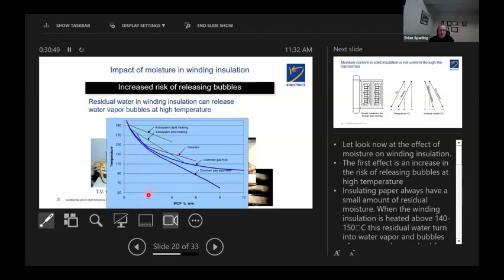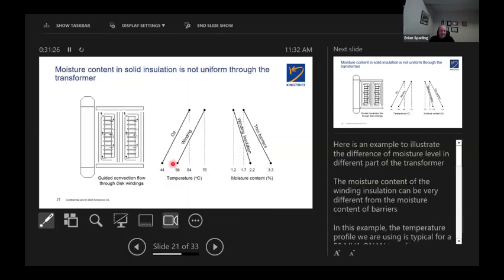But at 2% moisture content in the paper, bubbling is predicted to occur at a winding hotspot temperature of 140. If it's 4% wet, bubbling is predicted to occur at 110 degrees C hotspot, which a transformer by standard says you should be able to run forever, but only if the paper is dry to 0.5% water content in it. And that's the point of this understanding, why we want to know how wet is the paper, and all this research done by these gentlemen.